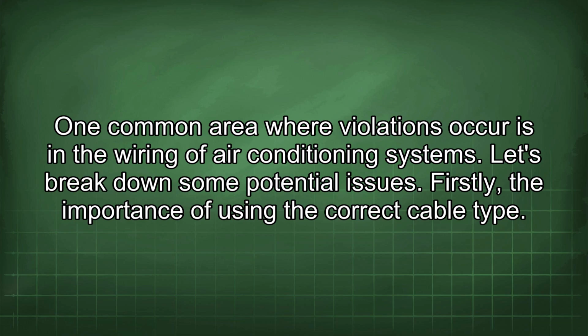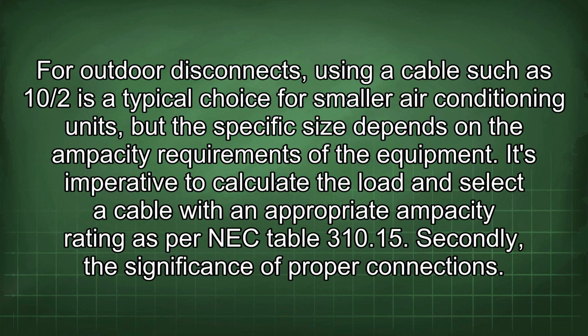Firstly, the importance of using the correct cable type. For outdoor disconnects, using a cable such as 10/2 is a typical choice for smaller air conditioning units, but the specific size depends on the ampacity requirements of the equipment. It's imperative to calculate the load and select a cable with an appropriate ampacity rating as per NEC Table 310.15.